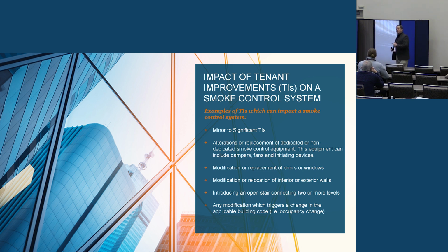We get in fights a lot with security teams. They'll be like, no, you can't pull a pull station and have the doors open. Okay, but you can't occupy the building if we don't, because the smoke control won't be adequate without that makeup air. So maybe the answer is we build different louver systems in an existing building. That may not be an option. So often what happens is security will override the life safety. And then when you need it, the system doesn't work. So security we tend to get in a lot of fights with on things like that. There's usually solutions if everybody's talking.